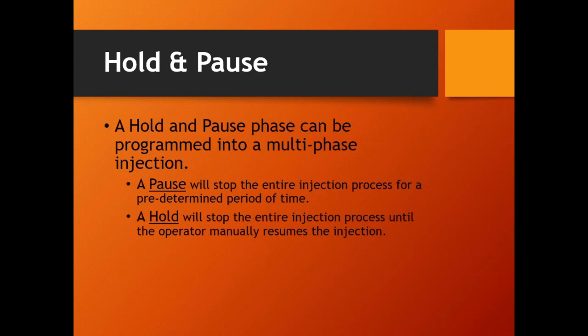I'll hit enter in phase 2. Instead of hold, I'll enter a pause, and I'll say pause for 5 seconds. Then go. So with a pause, the operator does not have to reinitialize the injector. The pause phase counts down to 0, then it moves on to phase 3 without the operator. All right, so that's the subtle difference between a hold and a pause. Next.